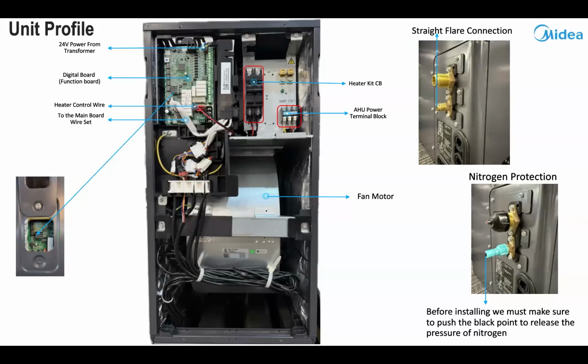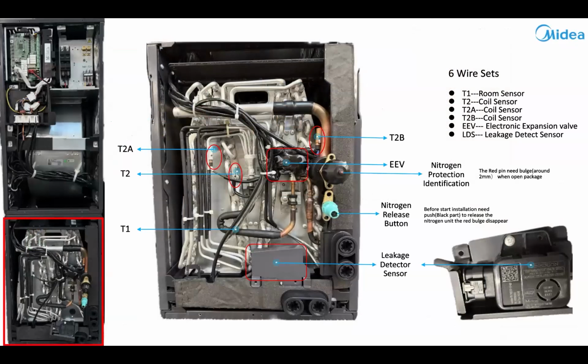All of our units come with nitrogen protection. Before you install it, make sure you release the pressure using the black button on this green cap here. They are all, excuse me, they are all straight flare connections. Intelligent error code check. So the homeowner can actually see the error code before they call. They can tell you over the phone if there's an error code, if you're so inclined to tell them to go down and look at it.